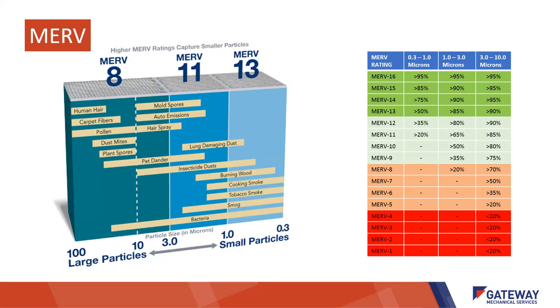We also have to keep in mind that a higher MERV rating filter may affect how the equipment operates. It needs to be compatible, because a higher rated MERV filter would do the same as a plugged filter—you won't have enough air coming through the system. So we're mindful of that when we prepare a service plan for you.